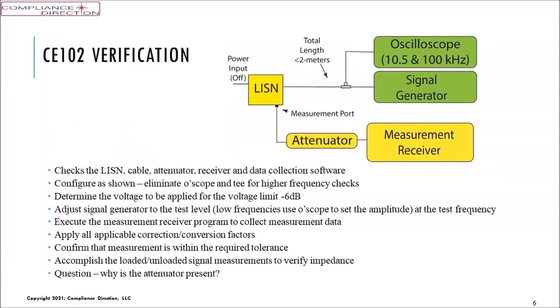CE102 has a similar kind of arrangement, except we're going to be checking voltage for the LISN, the cable, the attenuators, the receivers, the data collection software, much like anything else. And when I configure it as I show in the diagram there, after we get through the two low frequencies shown on the diagram, 10.5 kilohertz and 100 kilohertz, we would get rid of that tee and the oscilloscope for the higher frequency checks. We determine the voltage, minus 6 dB, adjust the generator, execute the software, apply the factors, etc., confirm we're in tolerance.